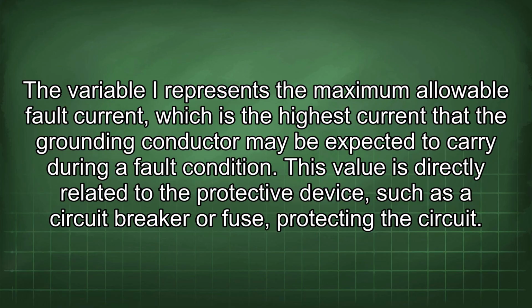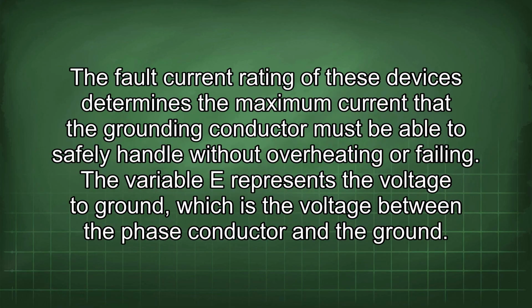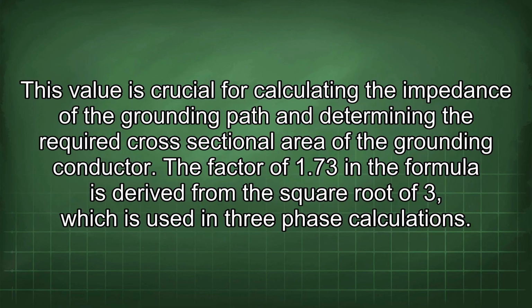This value is directly related to the protective device, such as a circuit breaker or fuse protecting the circuit. The fault current rating of these devices determines the maximum current the grounding conductor must be able to safely handle without overheating or failing. The variable E represents the voltage to ground, which is the voltage between the phase conductor and the ground. This value is crucial for calculating the impedance of the grounding path and determining the required cross-sectional area of the grounding conductor.